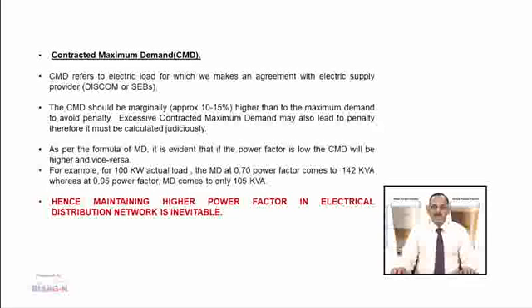Contracted Maximum Demand (CMD) refers to the electric load for which we make an agreement with the electric supply provider — that is, distribution companies or state electricity boards. The CMD should be marginally, approximately 10–15%, higher than the maximum demand to avoid penalty. Excessive contracted maximum demand may also lead to penalty, therefore it must be calculated judiciously. As per the formula of maximum demand, it is evident that if power factor is low, the CMD will be higher.